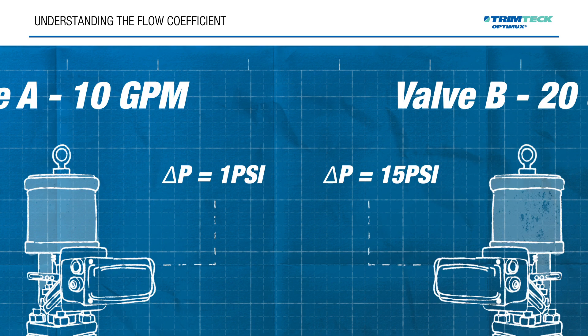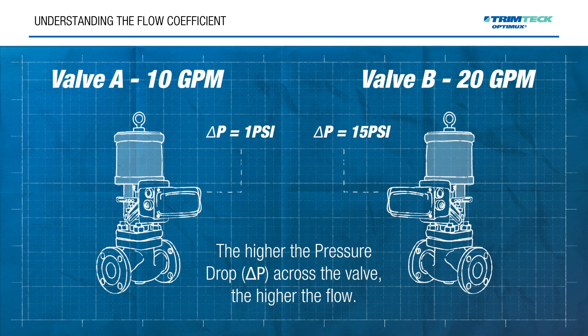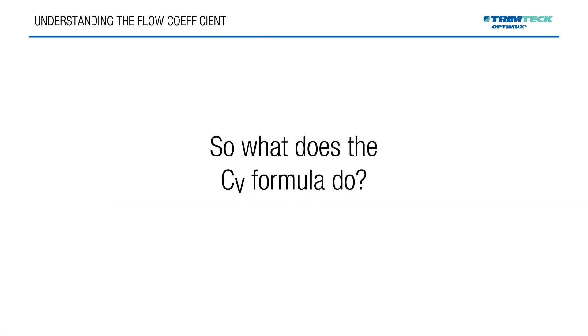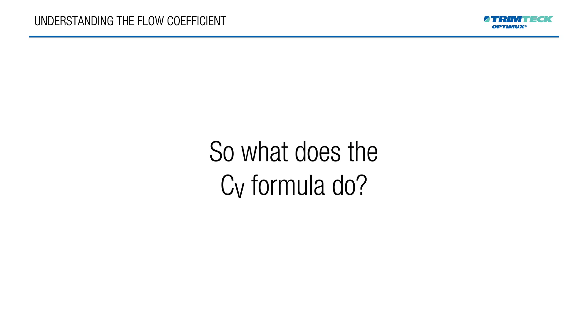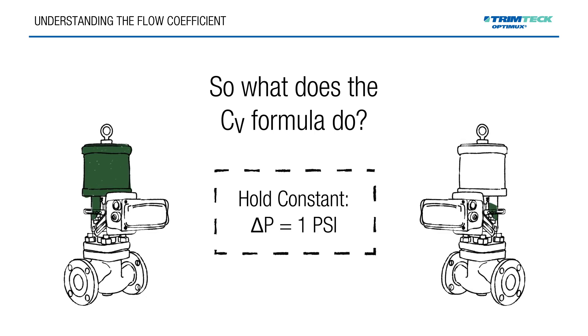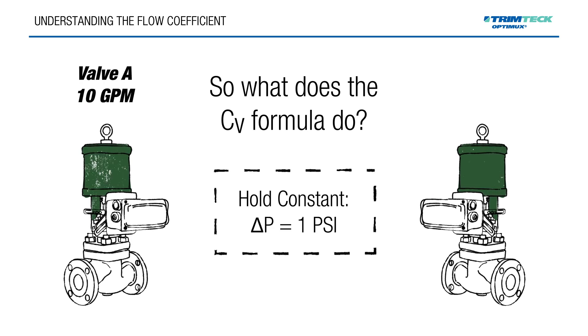The first concept to understand is that the higher the pressure drop across the valve, the higher the flow. That would at least in part explain why Valve B is flowing 20 gallons per minute versus Valve A flowing 10 gallons per minute. So what does the CV formula do? It holds the pressure drop at a constant of 1 psi so that we can better compare the two valves. Holding this pressure drop constant at 1 psi, Valve A still flows at 10 gallons per minute, but Valve B drops to 2 gallons per minute. So there must be some other variable at play.